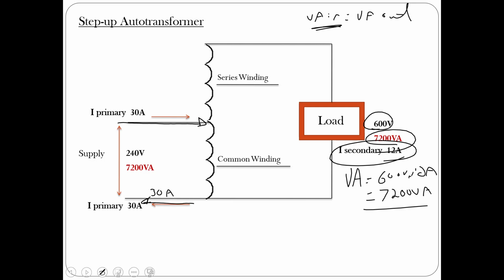All right. If we look at the load here, the load draws 12 amps. So current comes out always on the top, 12 amps, and it comes back, 12 amps. So if we use Kirchhoff's current law here, the series winding in this case is going to be exactly the same as the secondary current because there's only one path here. So we've got 12 amps going through the series winding.